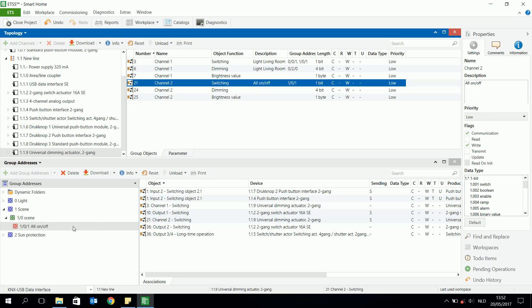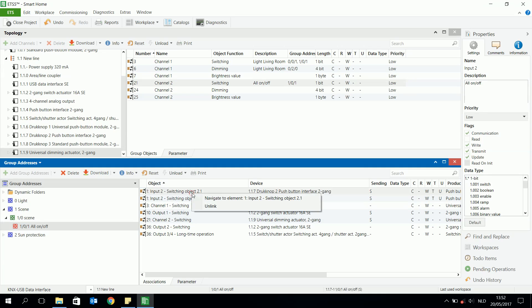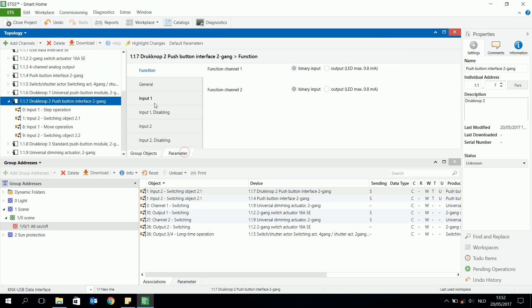One disadvantage is that in the group address you don't see immediately which object is off or on — you have to look into the parameters to see if it's off or on. So this was the way to program a scene using one group address.